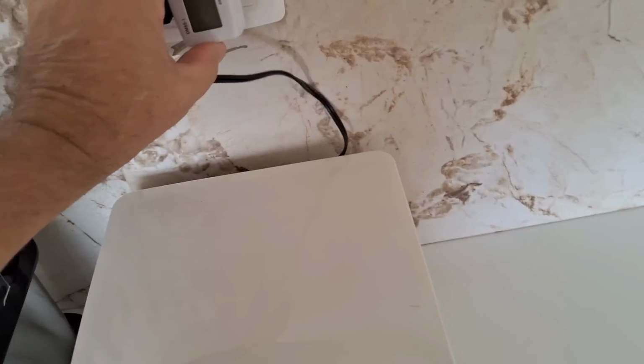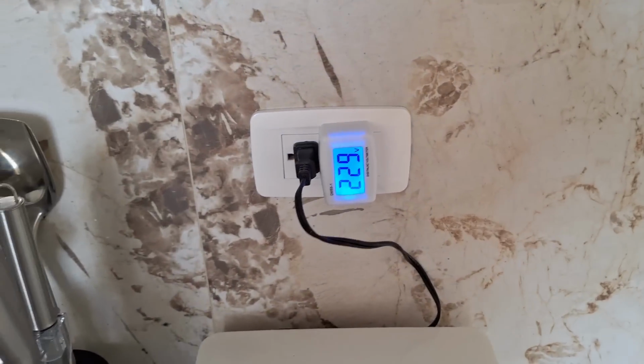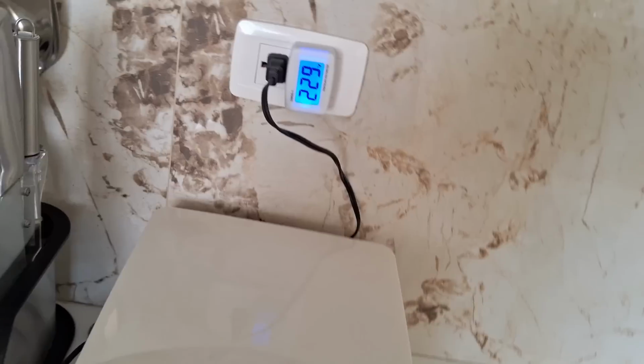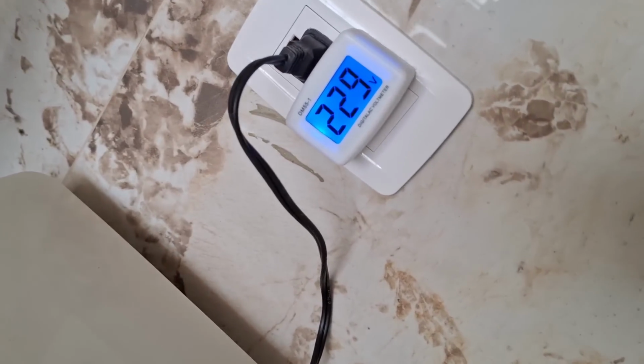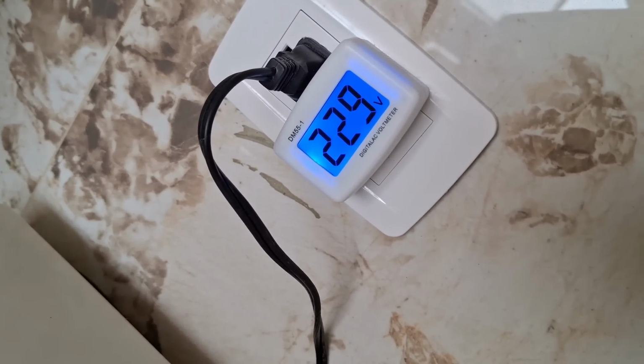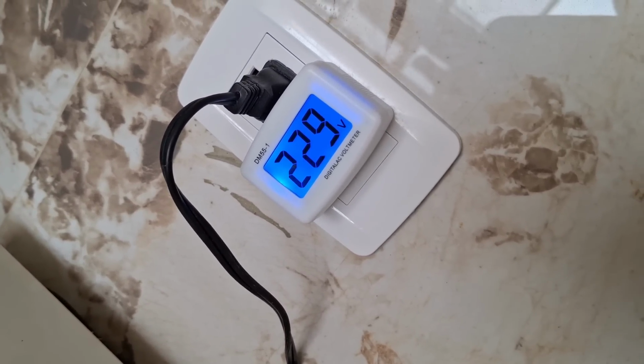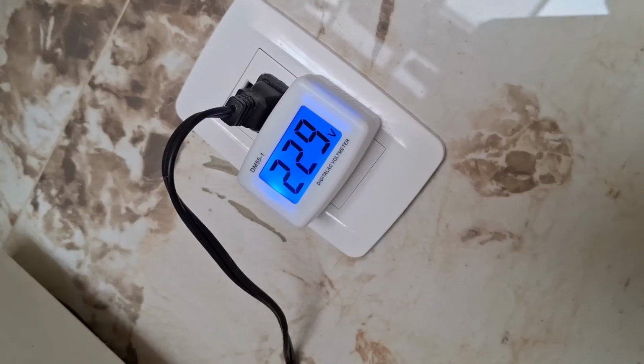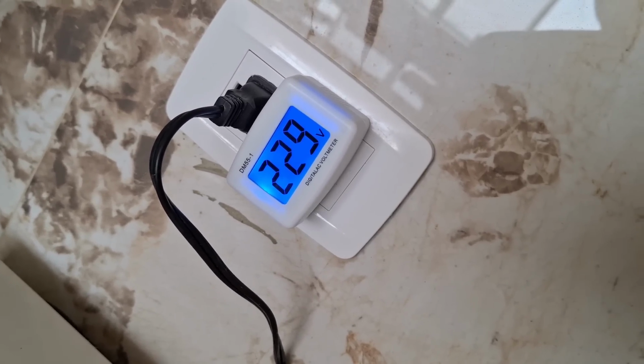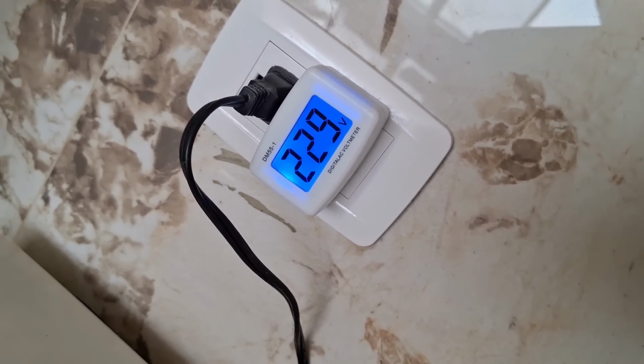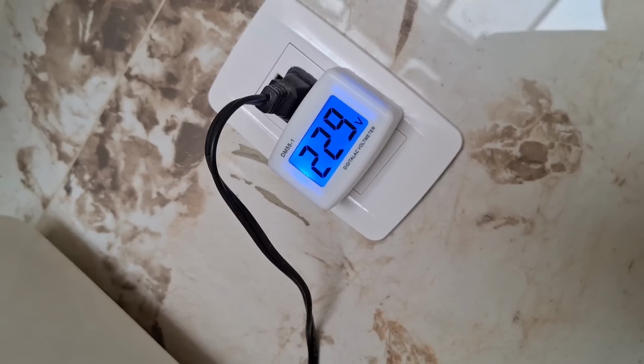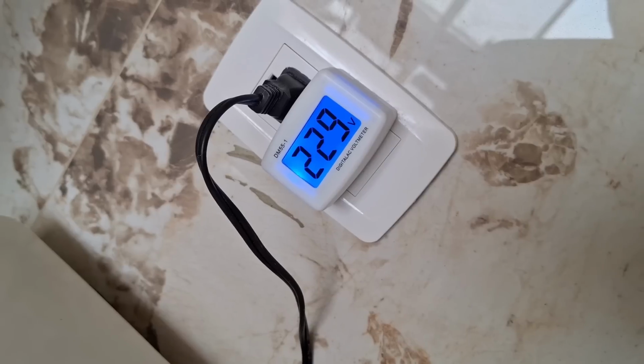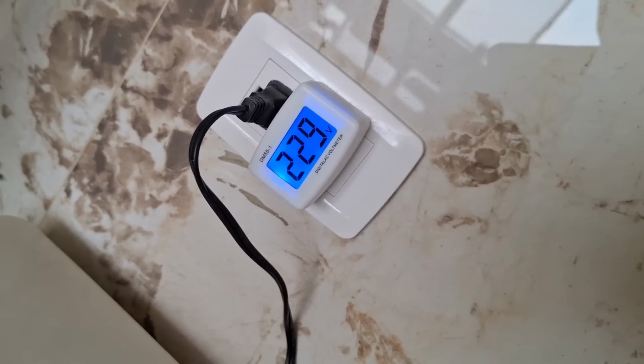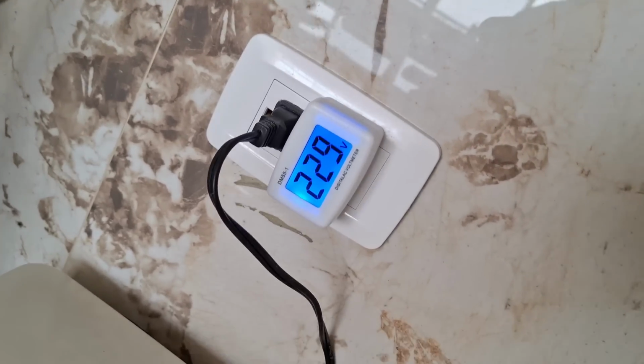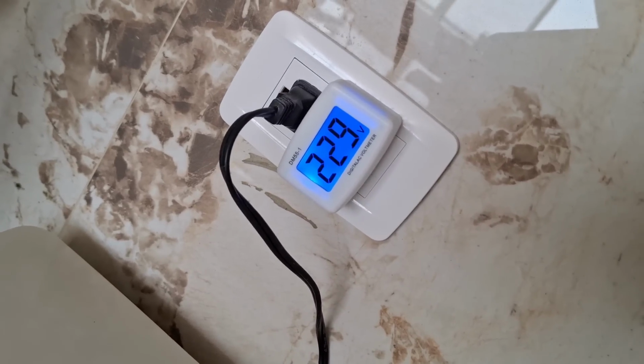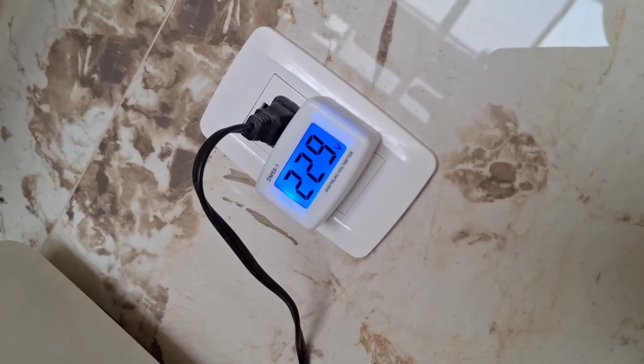It's pretty simple — you just plug it into any outlet and it tells you the voltage coming into the house. Right now it's reading 229, which is perfect. Anything around 220 is what you're looking for, and anything above that is okay, up to about 240. Right around 220, maybe just a little above, is the sweet spot. That's a good way to test for just a few dollars whether you're getting low voltage or not.